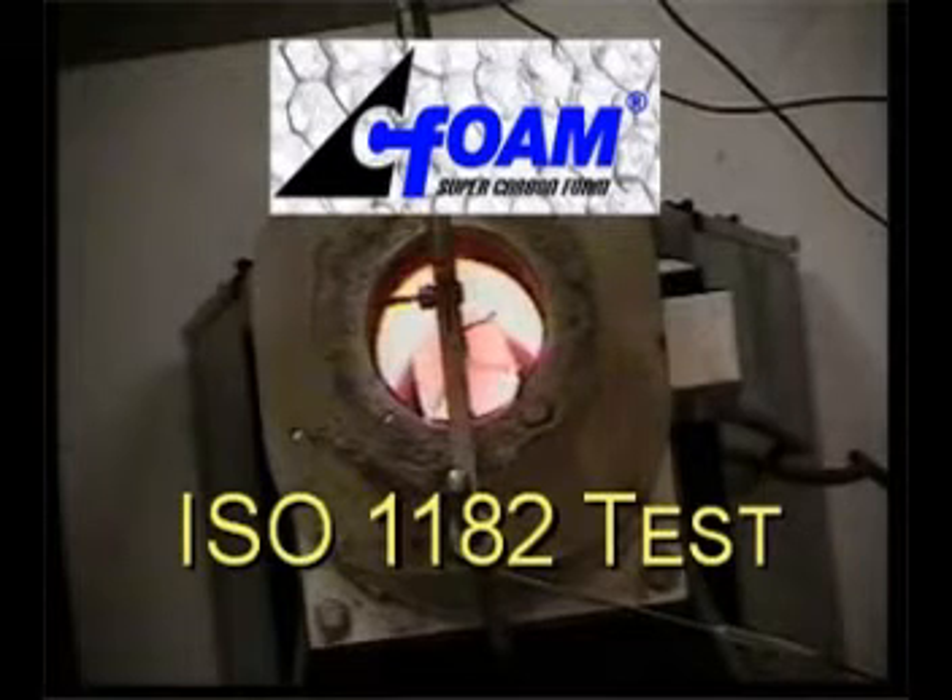The ISO 1182 test for non-combustibility is considered one of the most grueling tests for material undergoing fire qualification testing. The C-foam specimen, 45 mm in diameter and 50 mm high, is placed in the combustion chamber that has been stabilized at 750 degrees Celsius.